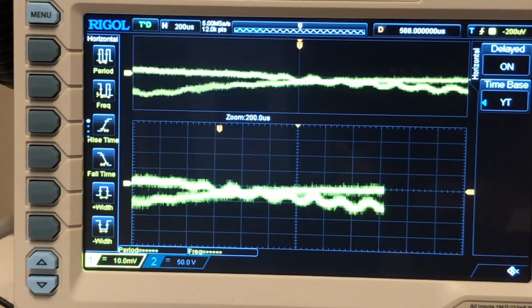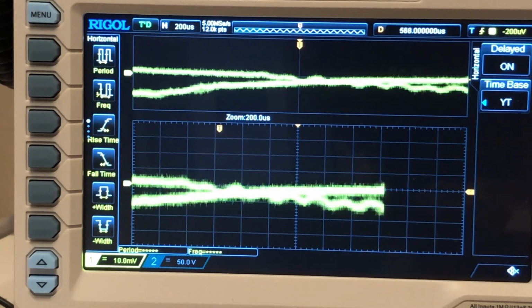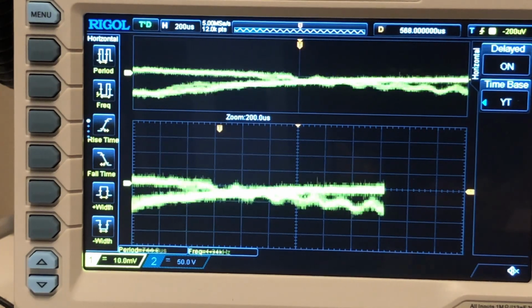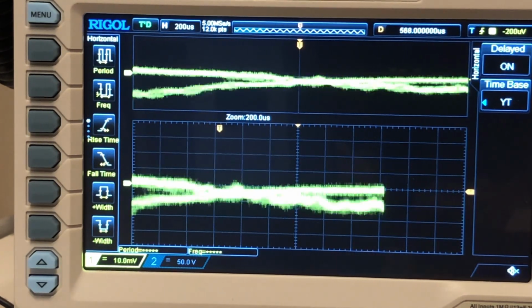The waveform in the lower part of the screen is the horizontally expanded waveform. Compared to the main time base, the delayed time base has increased the waveform resolution. The delayed time base should be less than or equal to the main time base.